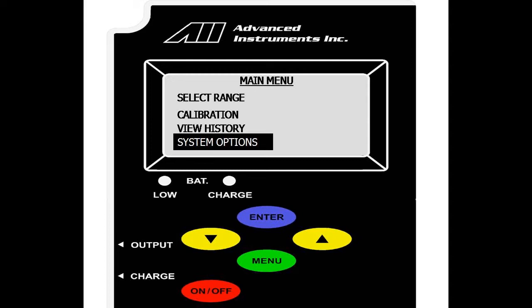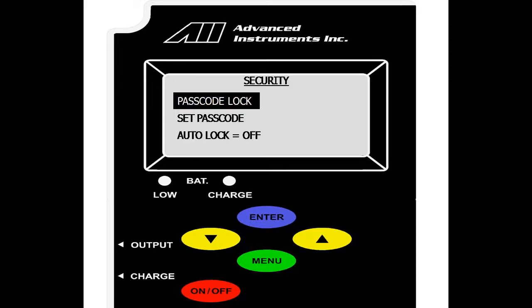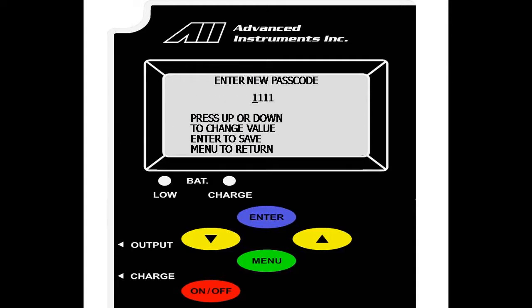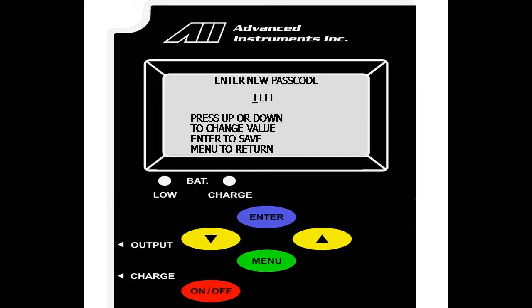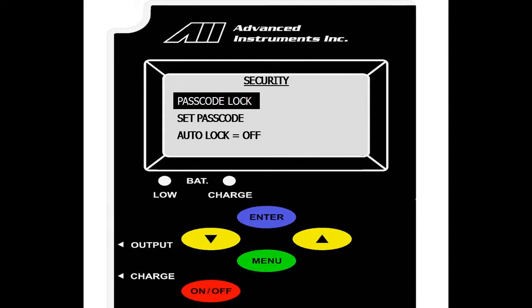We will now go over system options in the main menu. Select enter and we have security and define ranges. We will first go over security. In the security menu, you can set a passcode which is a four digit value used to lock the analyzer. Highlight set passcode and you enter your new passcode for the analyzer. Default is set as 1111. You hit up or down to change the value and enter to scroll over. Once your passcode is set, go to passcode lock and select enter.